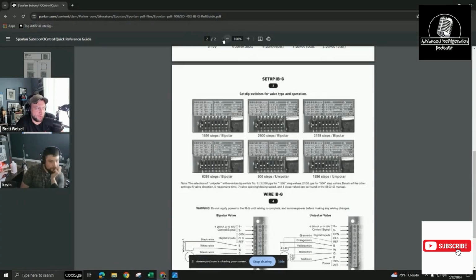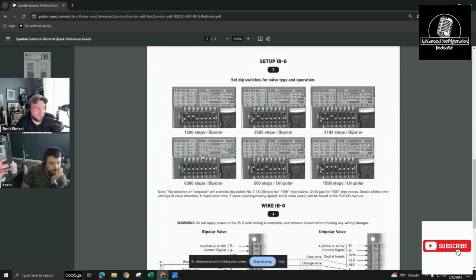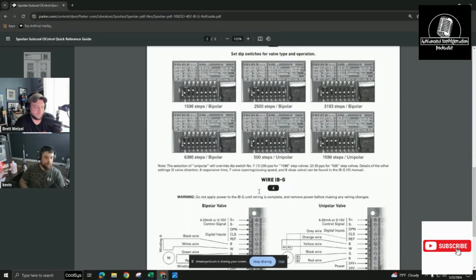Okay, let me take a crack at what you ended up doing. So the thing had probably 1596 because that covers the gamut there. And then at 0 to 10, 10 would be your 1596. So essentially you're putting out maybe 6 or 5 point something volts. Yeah, I think I went like 4.9 just to be safe, since it shouldn't open all the way anyway. So it throws off the scaling in the controller, it's almost double what it normally would be open, but I just sped up the PID and made it work faster. It worked, the rack is back running, it's functioning, running, and running a little bit better.